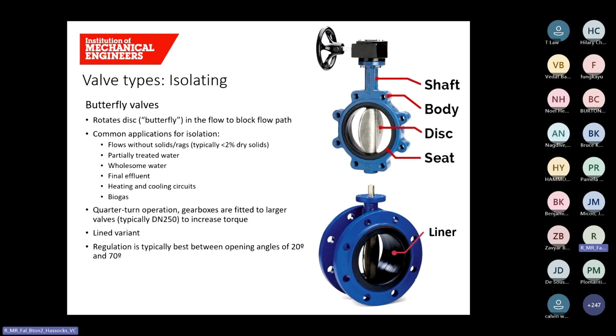Butterfly valves. These are simple in design, and they also allow for quick operation. The valve is named so because the disc supposedly resembles the wings on a butterfly. The valve is operated by rotating the disc 90 degrees into the flow path. And as we can see from the list of common applications, this is another versatile valve. However, it's not to be used where rag is present in the flow, as this can wrap around the disc, preventing full closure and potentially leading to some damage.